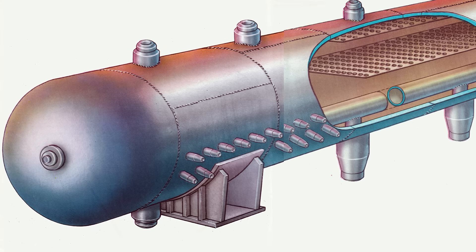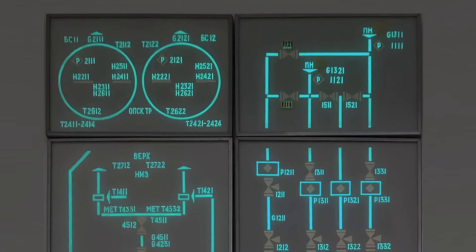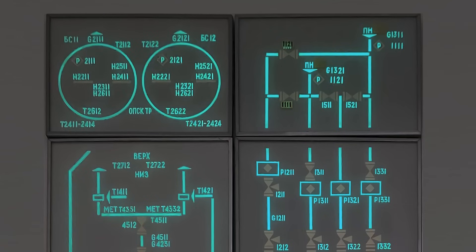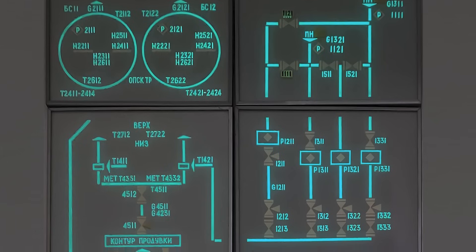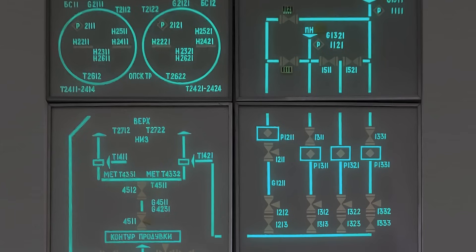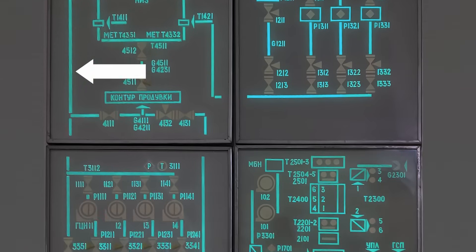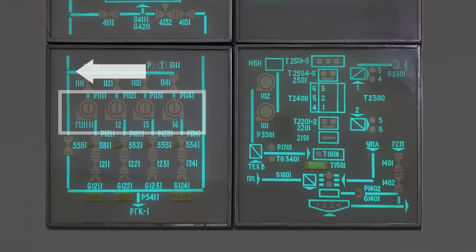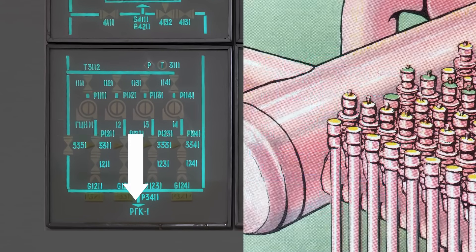So as you remember, inside the drum separators comes the hot mixture of the steam and water from the reactor. And you can literally see that in simplified way on this display as well. Steam is separated from water and then goes this way, to the turbines. Well, what happens in turbine we'll explore just a bit later. But to be short for now, from there it returns in a liquid form. It is so-called feed water and it is injected back into drum separators using these four lines. Three of them are for normal operation and one is a bypass for maintenance or reactor startup. From the bottom of drum separator water goes down to four main circulation pumps. These pumps push it into main delivery collector and then back to the reactor.